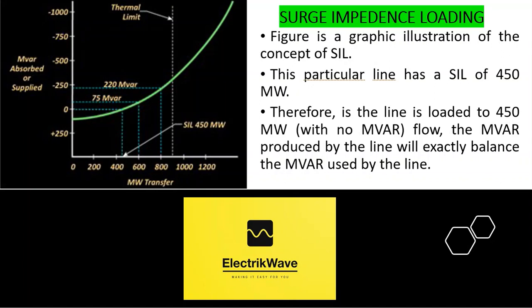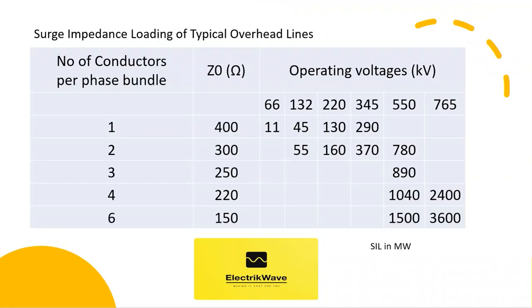The figure shown here is a graphic illustration of the concept of surge impedance loading. This particular line has a SIL of 450 megawatts. Therefore, the line is loaded to 450 megawatts, with no MVAR flow. The MVAR produced by the line will exactly balance the MVAR used by the line. Surge impedance loading of typical overhead lines in megawatts are given here for information.